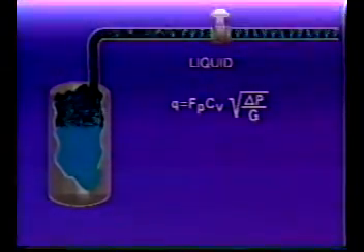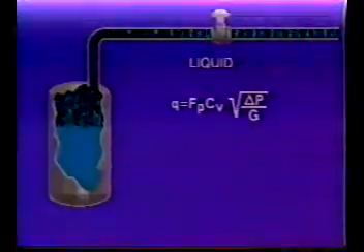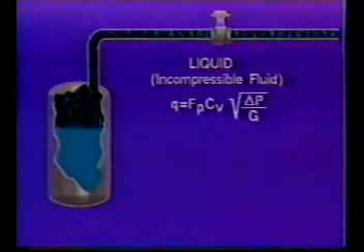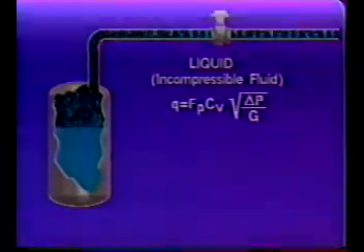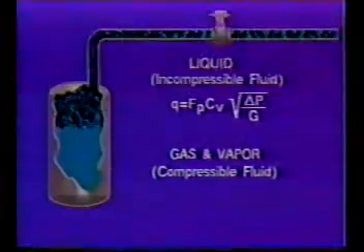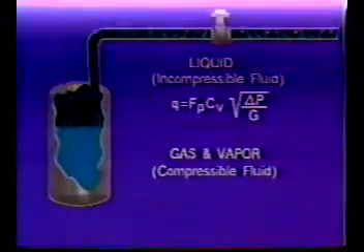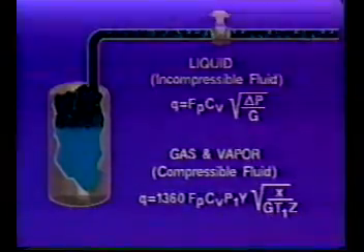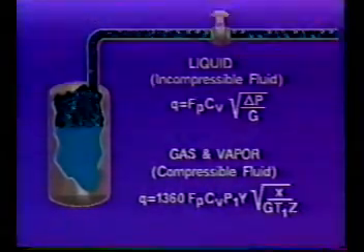For liquid flow, this was the basic working equation used. As you may recall, the development of this equation was based on flow of an incompressible fluid. However, gases and vapors are compressible fluids. As a result, a variety of correction factors are needed in the basic equation. Let's take a look at these factors, starting with the expansion factor, Y.